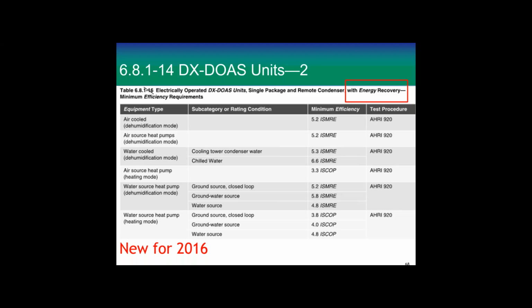So we do have requirements for DX DOAS systems. These are dedicated outside air systems, 100% outside air. We worked very hard with the manufacturers to come up with this. This is the minimum efficiency requirements with energy recovery, and this is a coefficient of performance. It's escaping me what this initial means, but what this means is it includes the humidity control in it and the energy recovery in it.